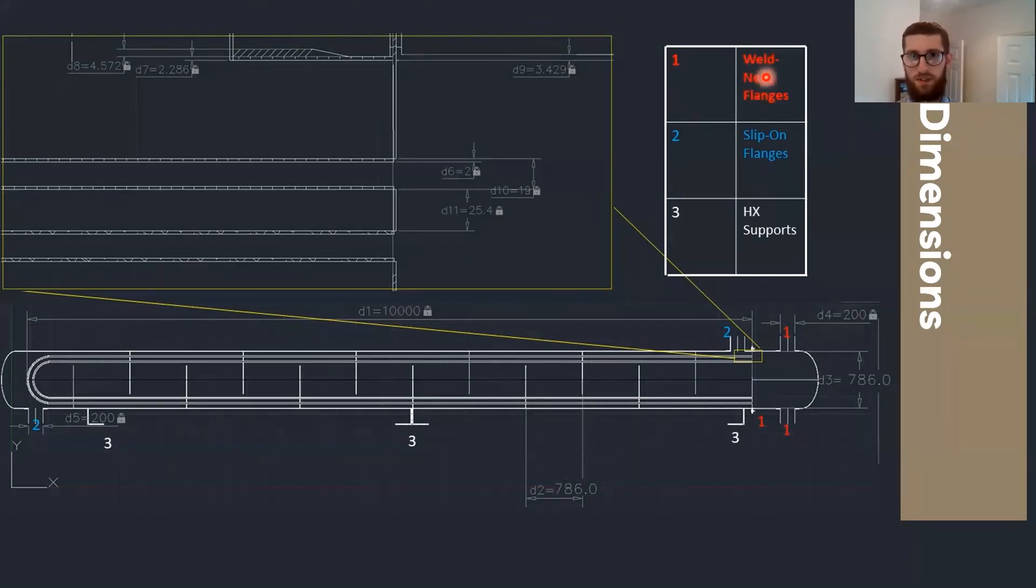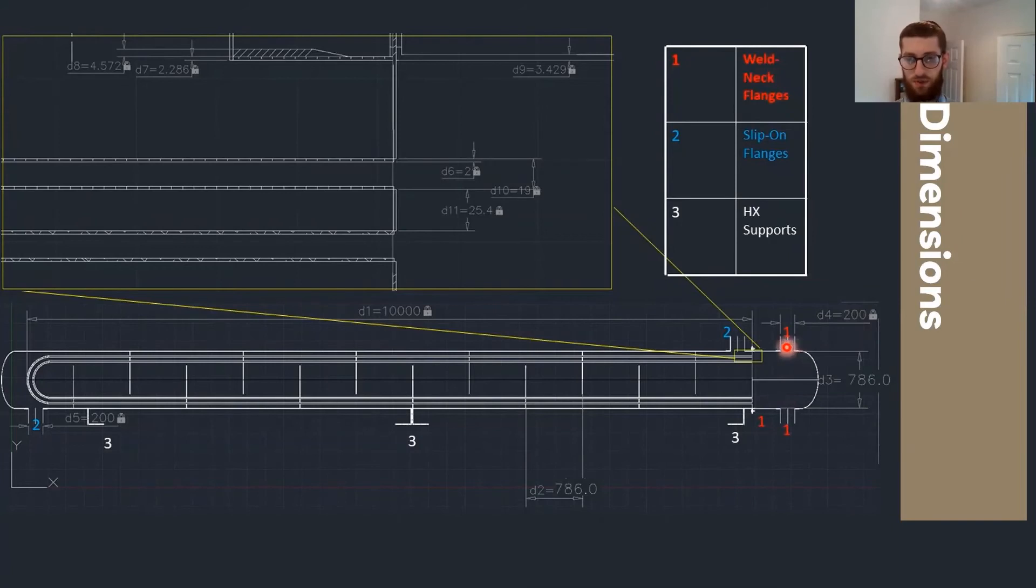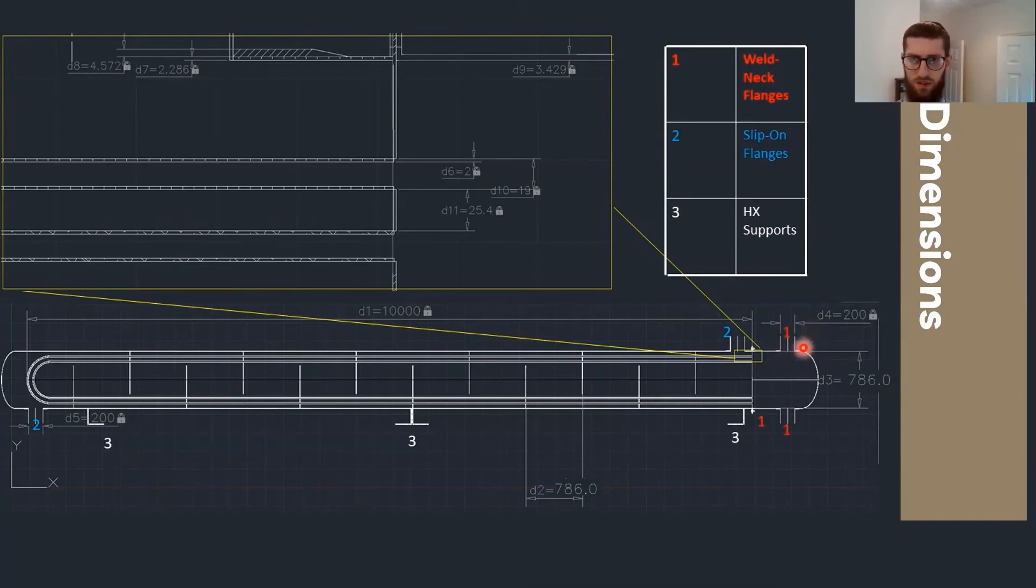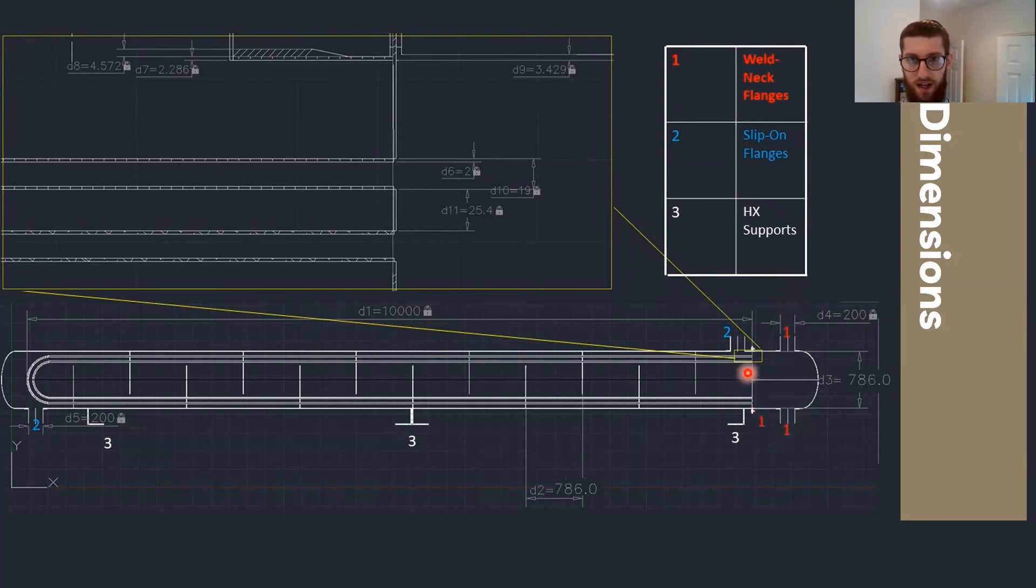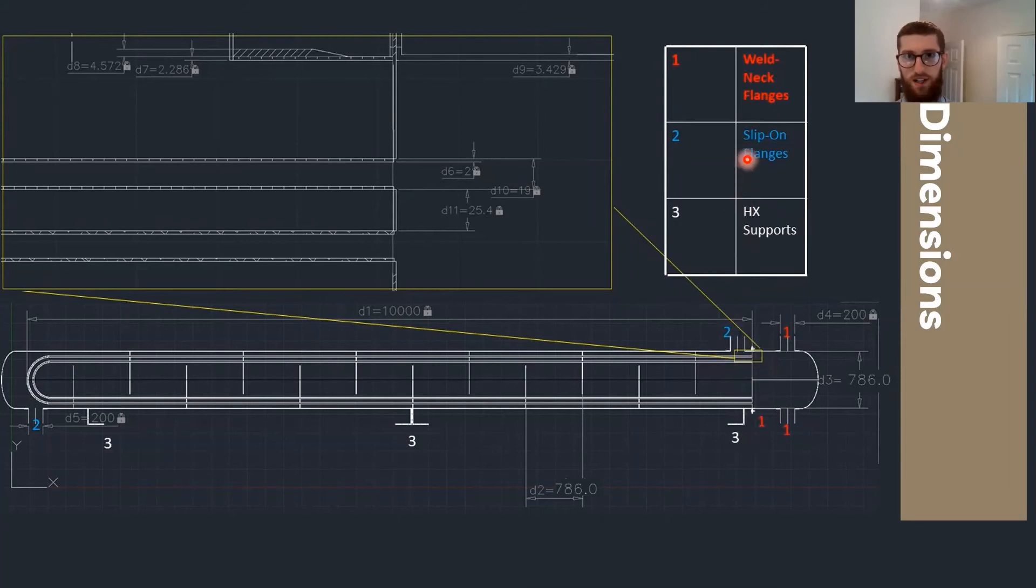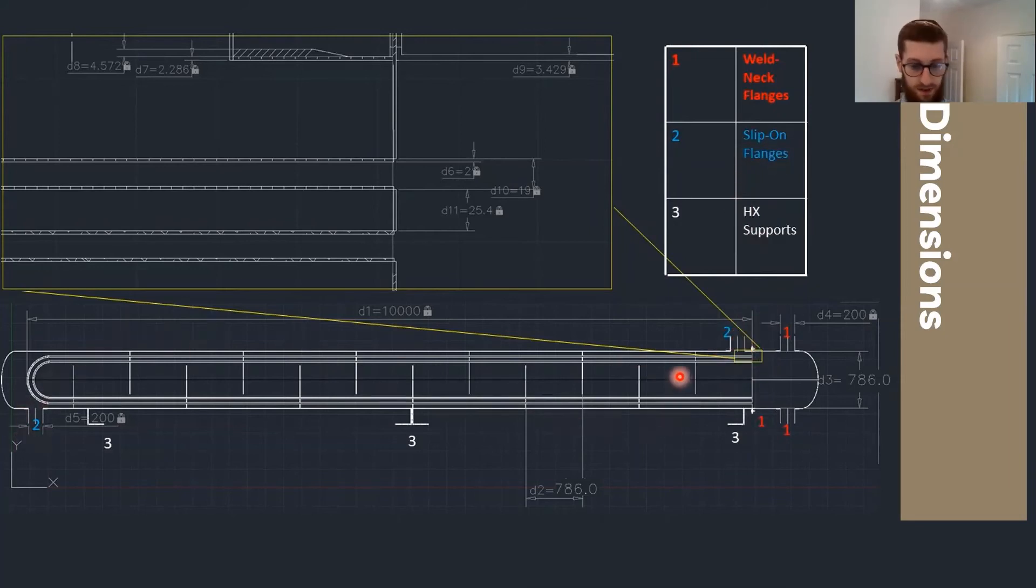I've labelled where the weld neck flanges, which are more expensive but more suited to the higher pressure of the gas, which is at 50 bar, where those are used on the tube side and to attach the tube side header to the rest of the shell, and the cheaper slip-on flanges can be used for the cooling water shell side fluid.